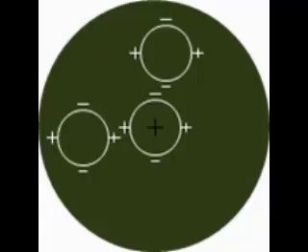For this particular instrument, focusing does not depend solely upon the sharpness of the target mires, but is accomplished by coinciding the double focusing circles into one circle.